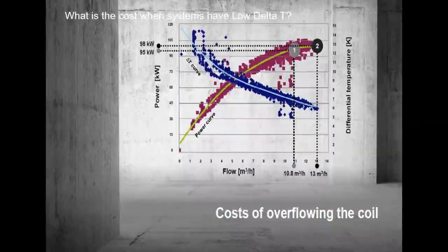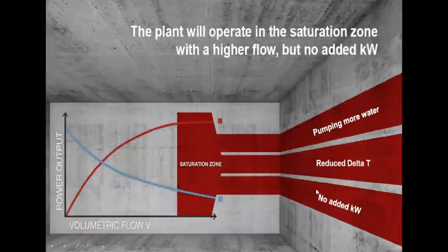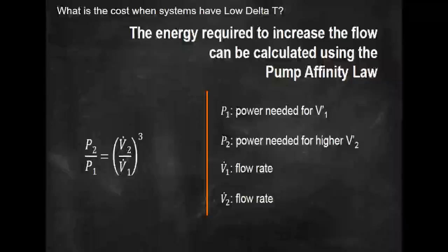But if I'm not able to give the design flow, which in this case is 10.8 cubic meters, and I slightly allow the valve to overflow to 13 cubic meters, because this curve flattens off, I don't see a commensurate increase in power. I see 3 kilowatts for my quite significant increase in flow. And that's because of the nature of the cooling coil. And if my coil is sized here to operate here, then I can very easily move into this saturation zone, and that's very bad. Let's have a look.